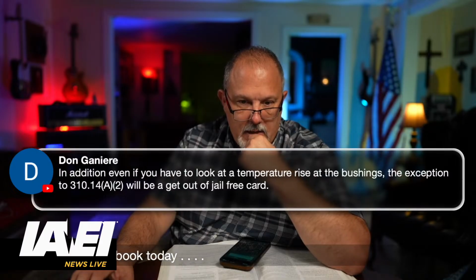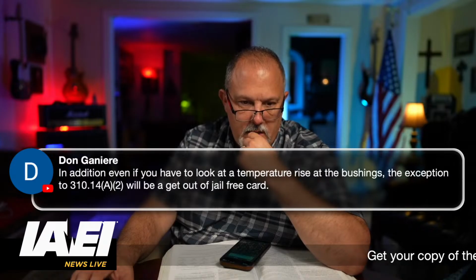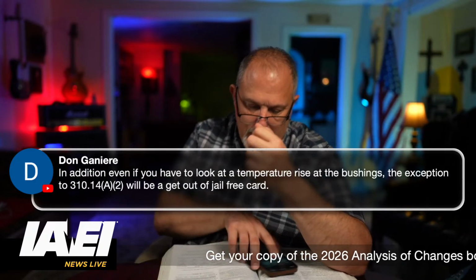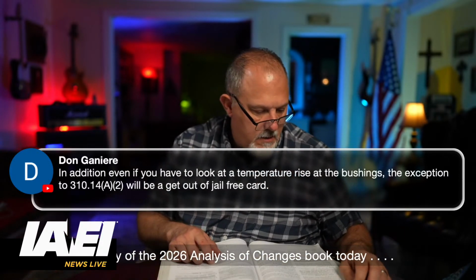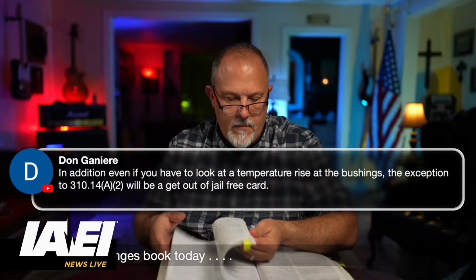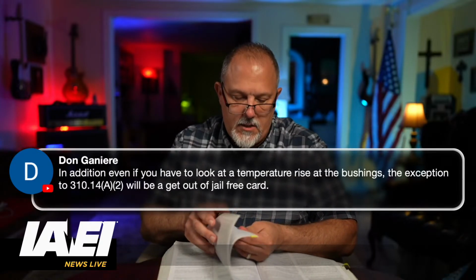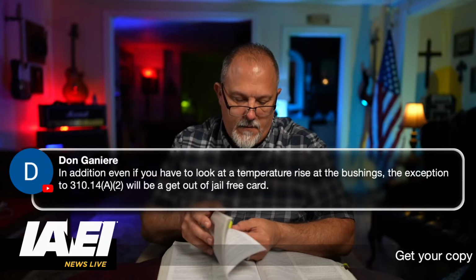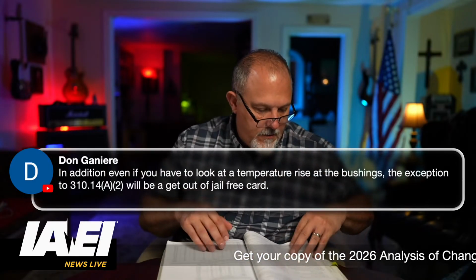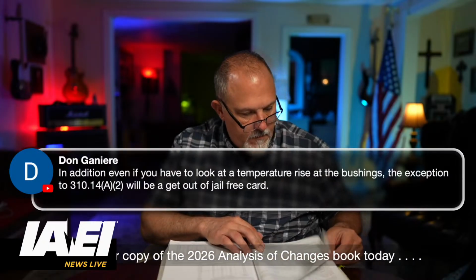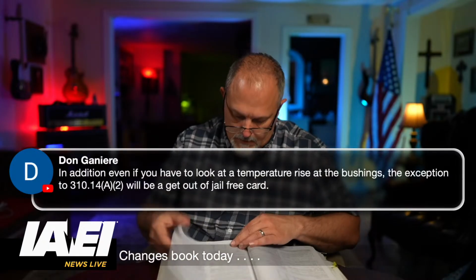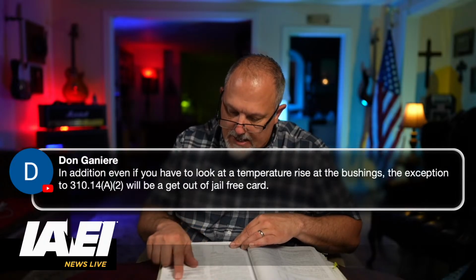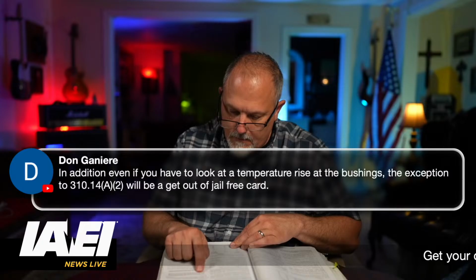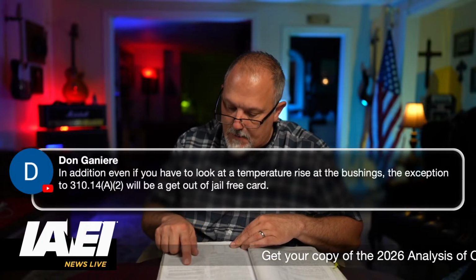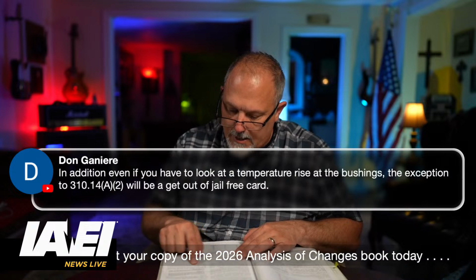Even if you have to look at the temperature rise at the bushing, the exception to 310.14(A)(2) will be a get-out-of-jail-free card. I'm not sure what you're talking about. 310.14(A)(2). 310.14 is ampacities for conductors. A is general. 2, exception: where different ampacities apply to portions of a circuit, the higher ampacity.